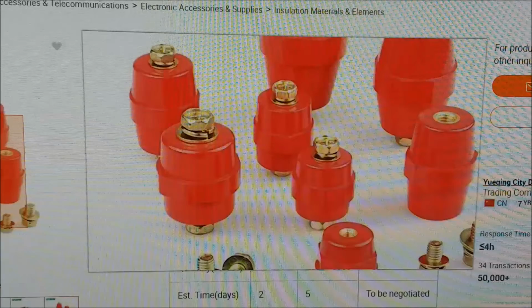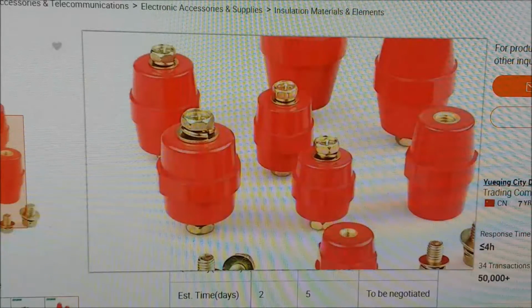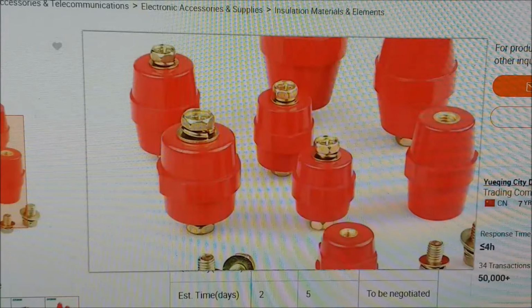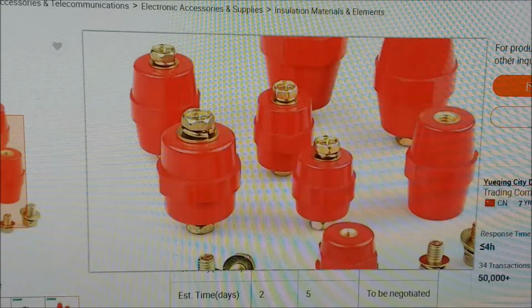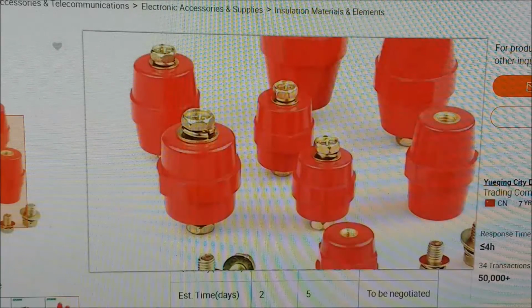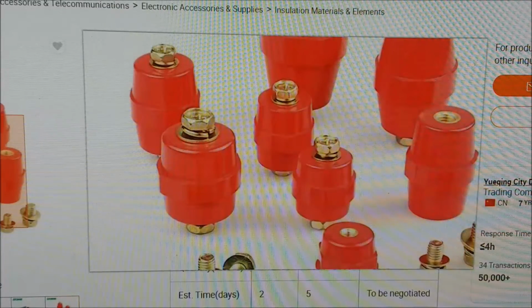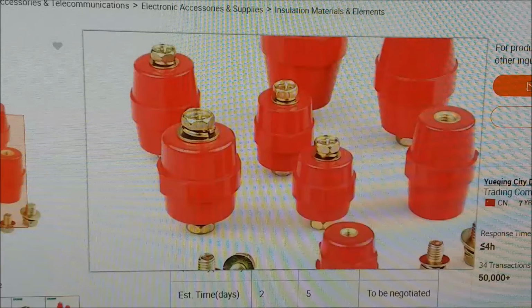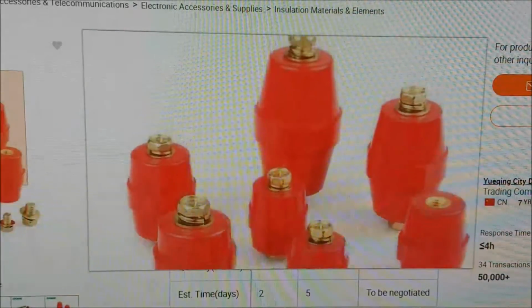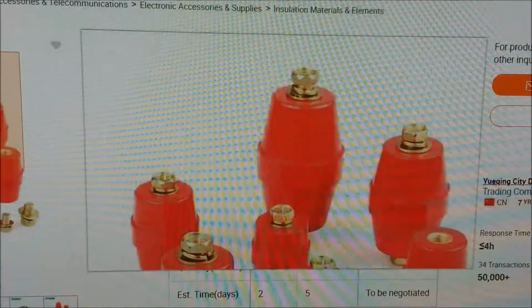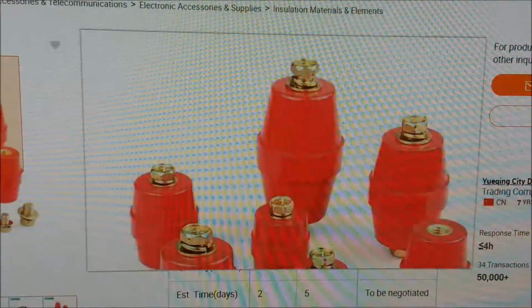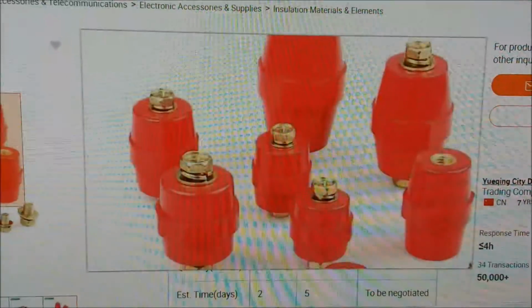So what we're going to do is put two pieces of 1.5 inch by 1/4 inch angle iron down the wall, one for positive, one for negative. Now these things have to be electrically isolated, otherwise they'd short to each other or to the wall. So the little red doobers we're looking at here are voltage isolators. They're called low voltage because they're rated 1200 volts or less. High voltage is like 33,000 volts, 100,000 volts.